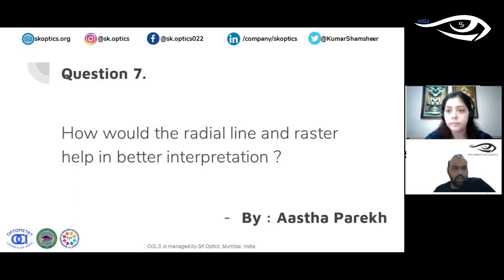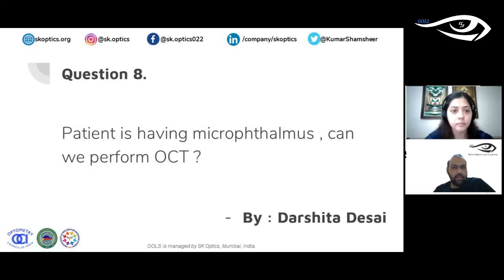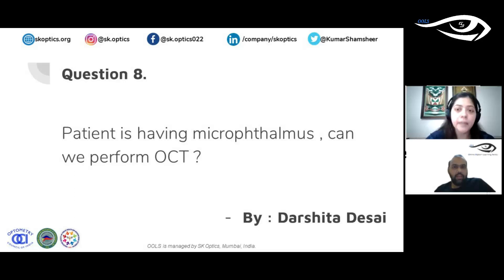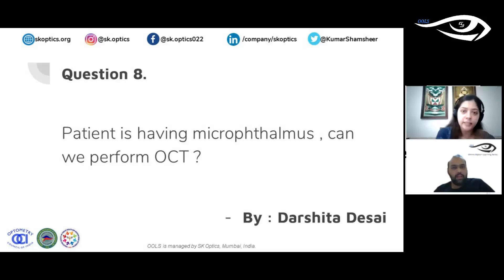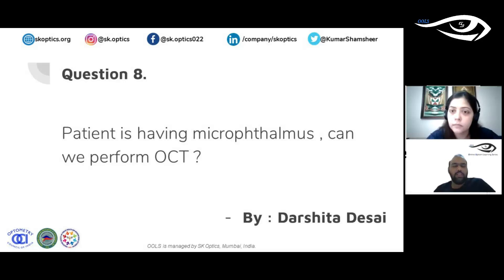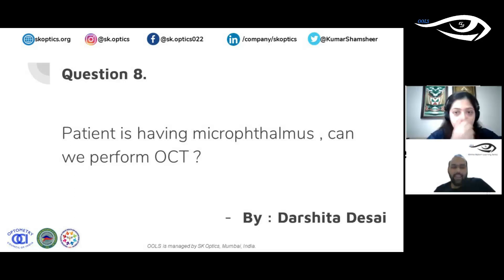Regarding OCT in microphthalmos: the eye is smaller, similar to a highly hypermetropic eye. As long as the media is clear, you can image. If the machine has an option to adjust for refractive error, set it to a higher hypermetropic value so it focuses the image appropriately. This option is also helpful in high myopes who won't be wearing glasses during the OCT scan. Check whether your specific machine offers this refractive error correction option.